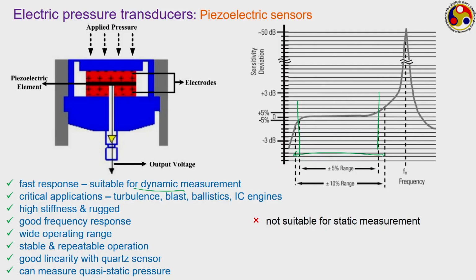So, they are not good for static measurement, but when we are looking for quite fast change in the output pressure or imposed pressure, then they are very good devices. Generally, they need expertise during installation. While mounting on a particular location, you need to be very careful and need to follow a suitable procedure. They can be susceptible to shock and vibration, leading to the cracking of the crystal or some rupture of the crystal material.